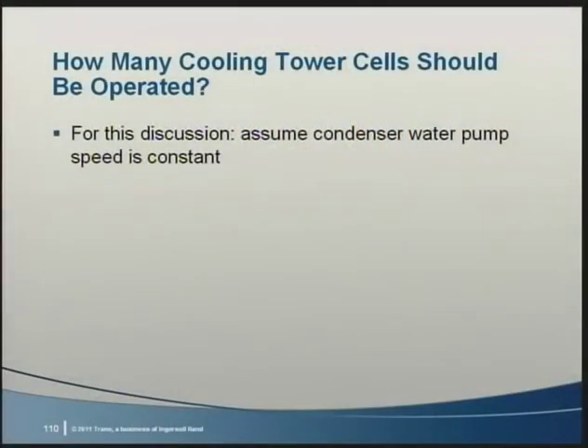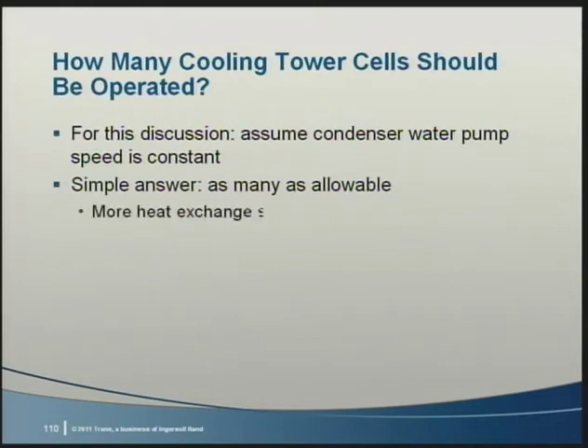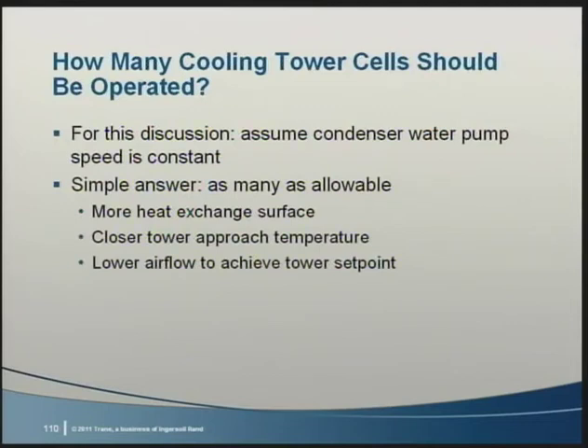If there are multiple chillers and multiple cooling tower cells, how many cooling tower cells should we operate when we have fewer chillers running? From a high-level standpoint, the answer is as many as possible. The reason is that cooling tower cells are heat exchangers. Since the expenditures have already been made, when possible, use more heat exchanger surface. The larger the heat exchanger surface, the better the heat transfer. The better the heat transfer, the closer the tower leaving temperature approaches the outdoor air wet bulb. The closer the approach temperature, the lower the airflow needed to make the water cold. And finally, the lower the airflow, the lower the tower fan power.